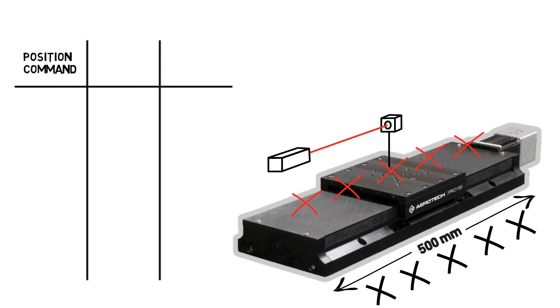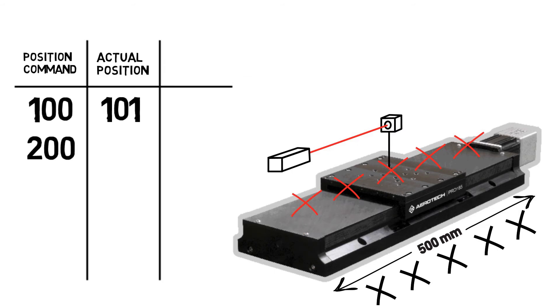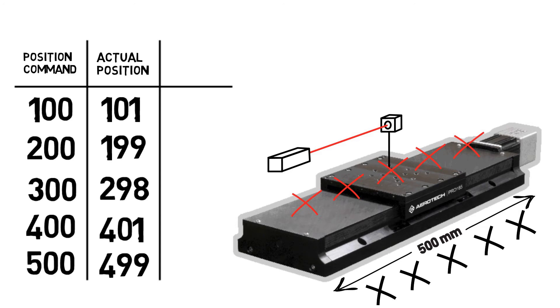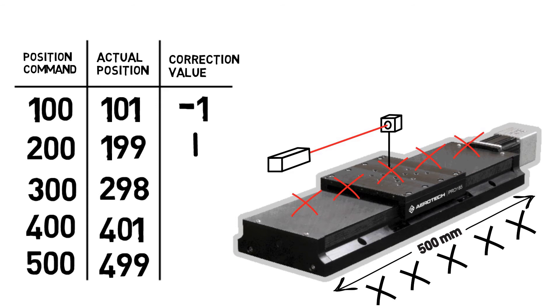As a simple example, we could collect the data every 100 millimeters and create a table of the commanded position and the actual position achieved. We then take the difference between the commanded and actual position values and create a third column, the correction value.